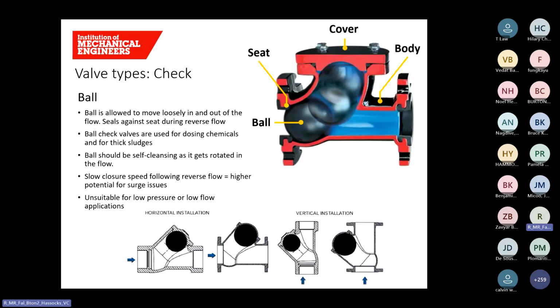A ball check valve is a type of non-return valve that uses a free-moving ball to block or allow flow. When fluid flows forward, the pressure lifts the ball off its seat, and that allows fluid to pass. When flow reverses, the ball returns to the seat, often with the help of gravity or a spring. That seals the passage and prevents backflow. Very simple in design, the ball is the only moving part. These are commonly used in chemical dosing systems and for thick sludges. The ball itself is usually made from NBR or coated with a polyurethane. It's also available in various weights to suit different system requirements. It should also be self-cleansing as it gets rotated in the flow. The ball check valve has a slower closure speed following a reverse flow, and that results in a higher potential for surge issues. The valve is unsuitable for low pressure or low flow applications, as the ball may not lift.